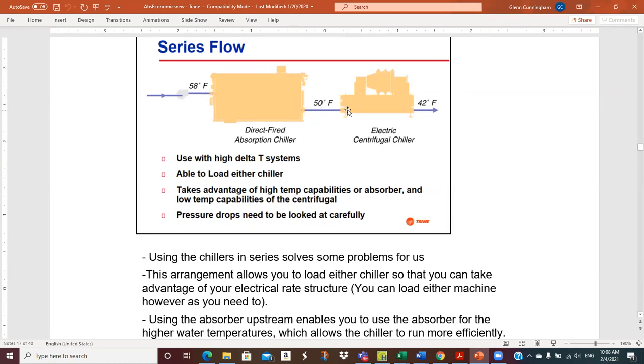So in this scenario, we can load either chiller we want to. It takes advantage of the high temperature capabilities of the absorber and the low temperature capabilities of the centrifugal. And so we've got another note down here. They'll talk more about that. The issue right now is that we're pushing all of the water through both chillers. Well, that's fine if we're using both chillers, but what if we're just using the absorber? Well, we don't want to pay for the pressure drop across the evaporator in terms of the chill water flow. And so as drawn, that would be a detriment.